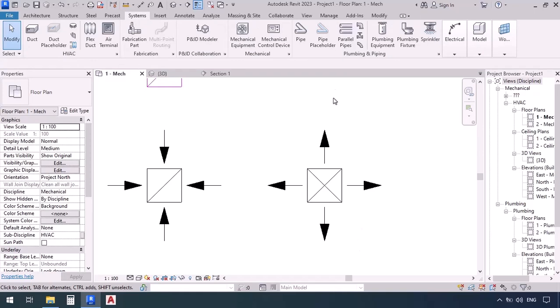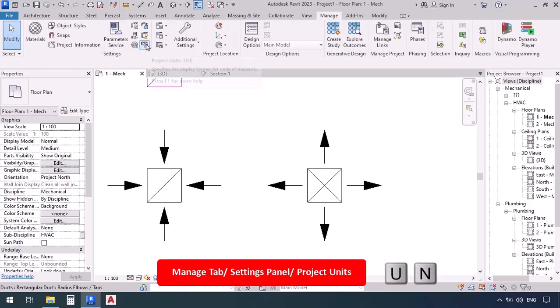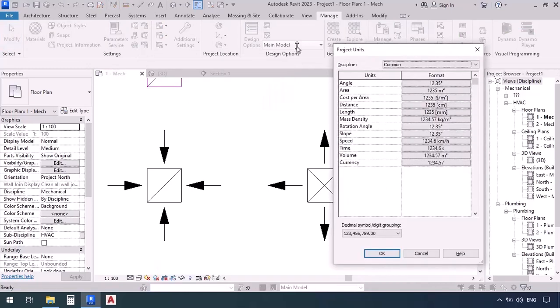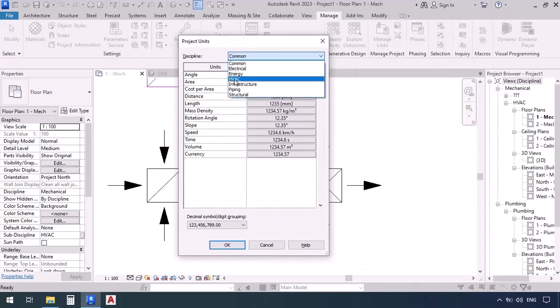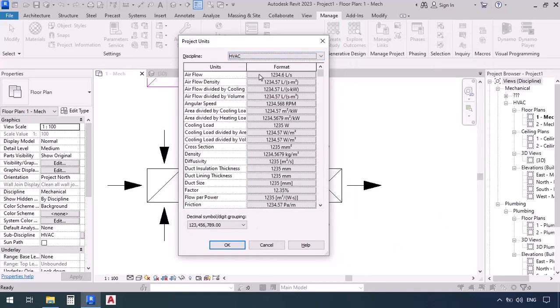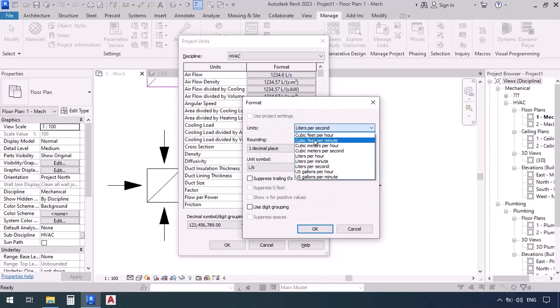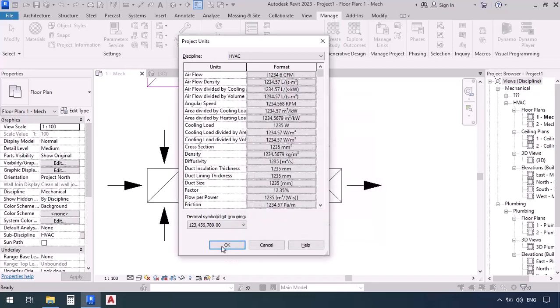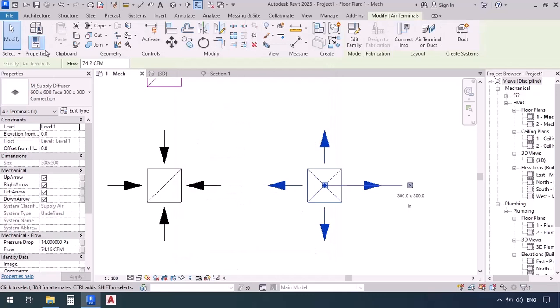We might also have the CFM unit in the plan — we can change that if necessary. We've talked about editing units before: go to the manage tab and click on project units, or use the UN shortcut, then go to discipline HVAC. In the airflow section you can change liters per second to CFM — cubic feet per minute. Set one decimal place and for the unit symbol enter CFM, which is the most common unit. Now close those windows and as you can see, 35 liters per second has been converted to 74.2 CFM.